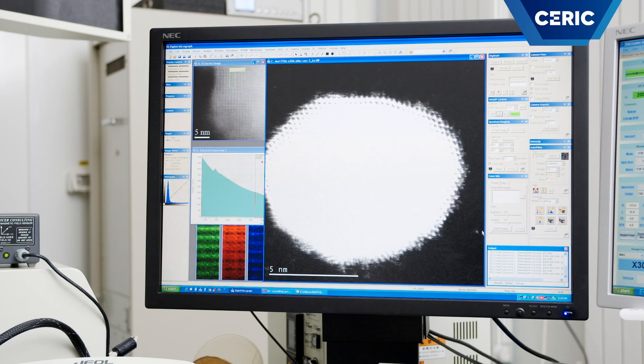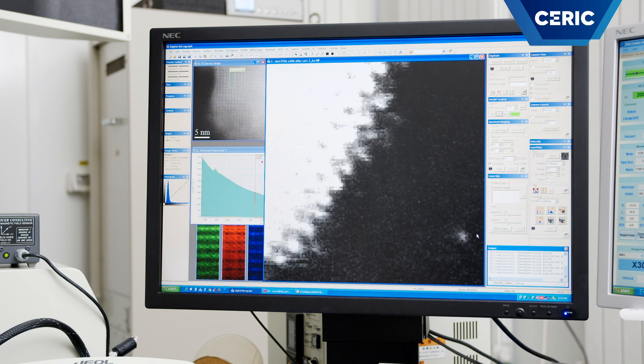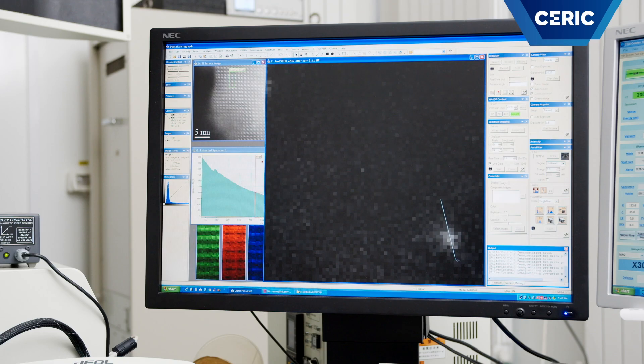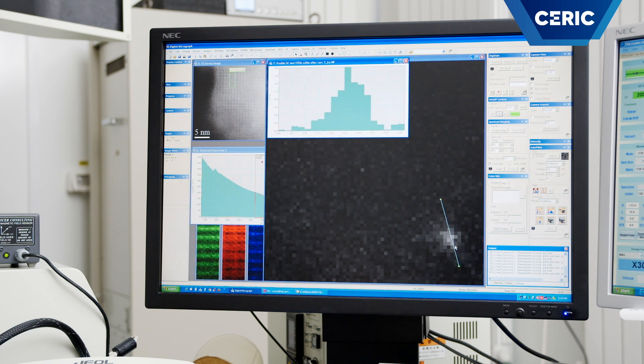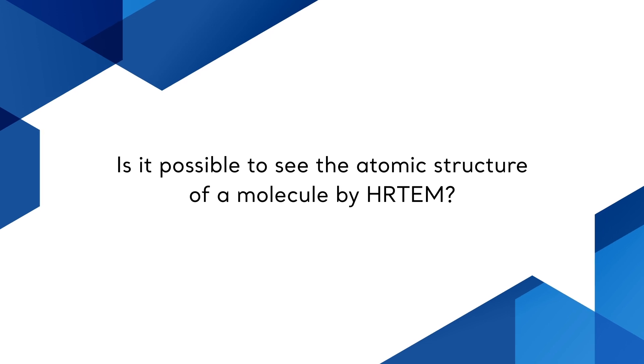Although HR-TEM refers to visualizing the atomic structure of materials, it is not possible to use this technique for imaging single atoms. However, this can be done in certain conditions using the aberration-corrected STEM mode. The imaging principle in HR-TEM is based on the interference between the diffracted electron beams emerging from a crystalline specimen. Therefore, it is not possible to see the atomic structure of a single molecule. Moreover, it is not possible by any electron microscopy technique to observe the atomic structure of amorphous materials, like glasses or polymers.